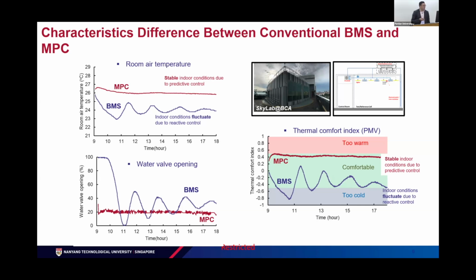So the second figure, if you look at how the hardware is behaving in terms of a conventional PID control versus how it's behaving in terms of MPC. Usually for your PID, you have a time control of these hardwares where your reactive system is measuring the temperature inside the office space and then reacting to whatever thermal load has occurred inside the building. So it's always swinging from highs to lows in case of the PID-based BMS control. Whereas for your MPC, you are actively controlling your actuators so as to provide a very steady and stable indoor condition for your occupants.